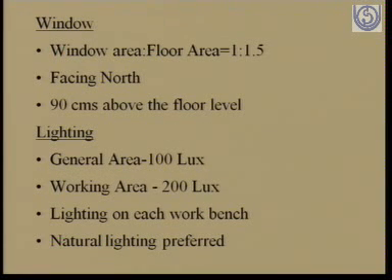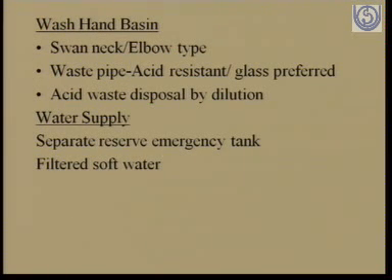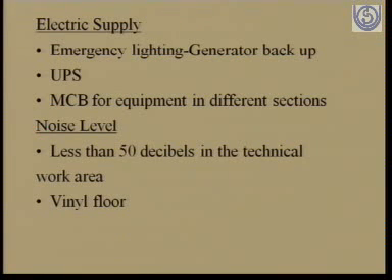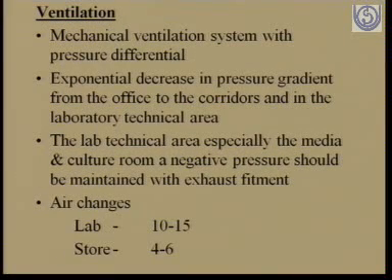Lighting, as you can see on your view file: approximately 200 lux is required wherever there are working areas, sample collection and all those areas. Wash basins should be available in plenty, especially at the workstations where constant hand washing is required, and soft water is required all over the laboratory. For electric supply, you need a generator backup and UPS. This is required for air conditioning and for all the equipment, and the noise level should be preferably below 50 decibels.